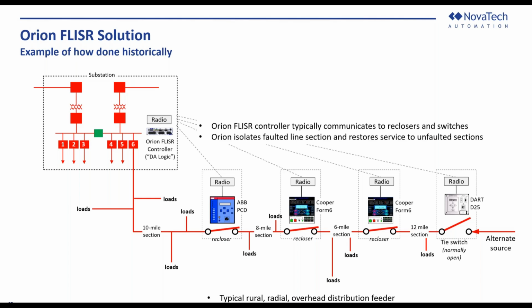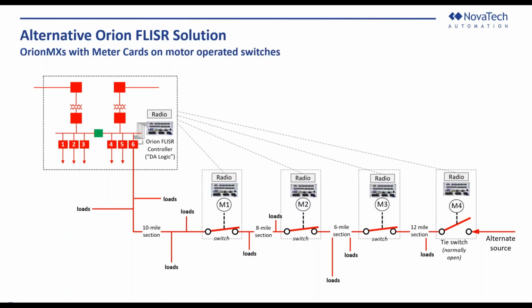What we're proposing is an alternative approach. We can imagine you have a substation with a similar line, a rural station with motor operated disconnect switches. Here we're demonstrating M1, M2, M3 as three motor operated disconnect switches, and then M4 being the tie switch, which is also feeding in from an alternate source. In case the feed from feeder 6 goes bad, or there's an outage on this line, an alternate source can come in and play the role there.